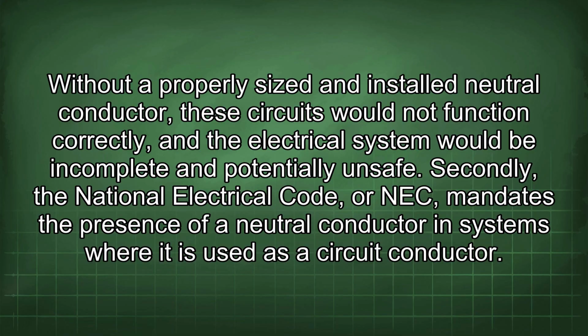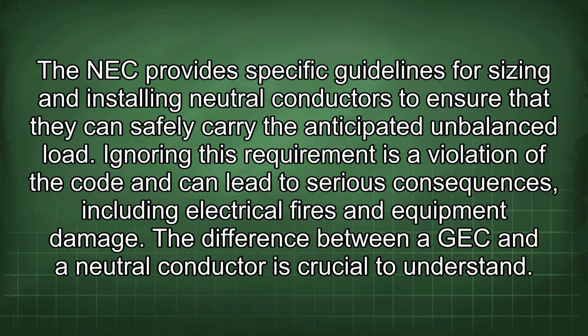incomplete and potentially unsafe. Secondly, the National Electrical Code, or NEC, mandates the presence of a neutral conductor in systems where it is used as a circuit conductor. The NEC provides specific guidelines for sizing and installing neutral conductors to ensure that they can safely carry the anticipated unbalanced load.